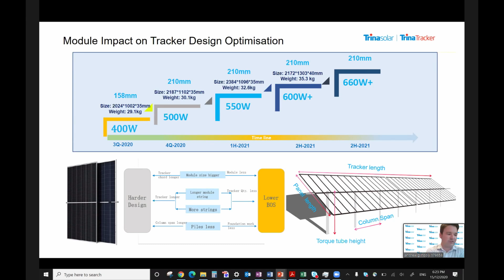With the Trina modules, we use the M12 210 millimeter wafer. So even though the module wattage is around 550 or 600, there are fewer cells connected electrically within those modules, so the voltage is actually quite low, in the high 30s or low 40s open circuit voltage. We're running strings up to 40 modules per string on our trackers now. That increases the north-south length of the tracker, and that increases the propensity of the tracker structure to second order dynamic effects such as torsional galloping and so forth. These are all the considerations going into it.